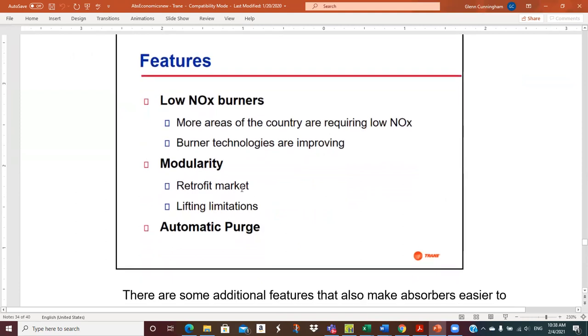Okay, so other features, low NOx burners. When you burn natural gas, you're going to produce some NOx. Now, there are different burner technologies, low NOx burners, obviously designed to reduce the amount of NOx. Depends on where you're putting these gases up. If you're in a non-attainment area where NOx levels are high, you have to be really careful, as they will limit the amount of NOx that you can put up from a given piece of equipment. You have to get a permit for it, and the permit will list the NOx, and you have to perform periodic testing. Power plants have to do continuous testing. They call it CEMS, continuous emission monitoring systems.